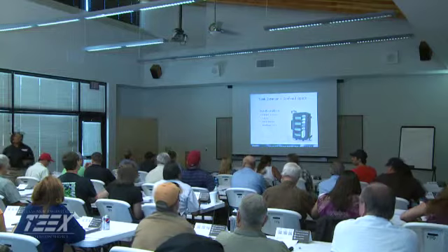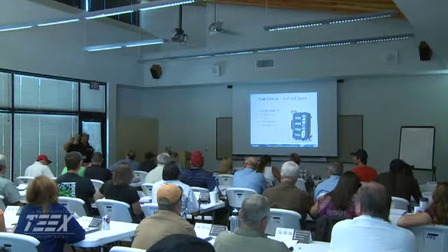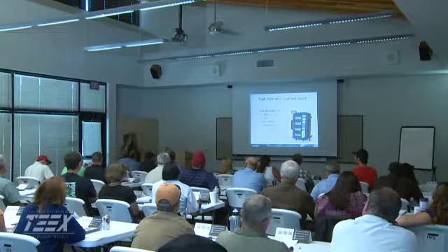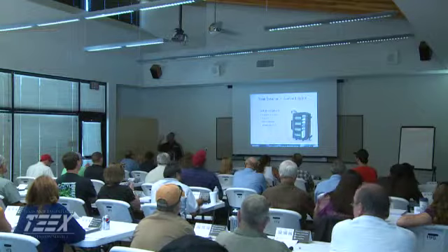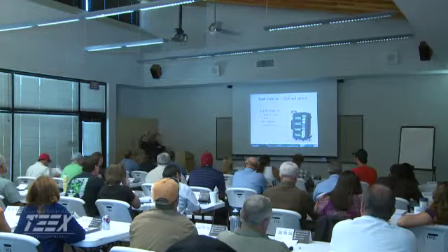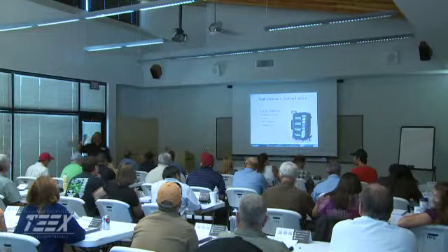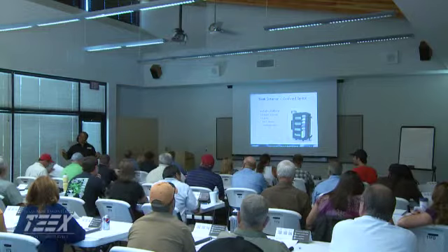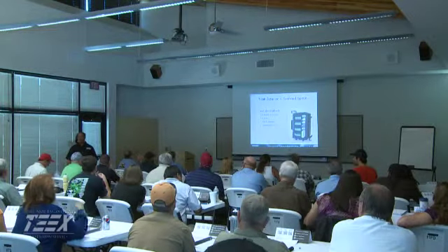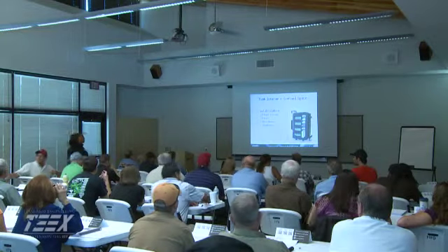It's real big. You're absolutely right. It is real big. Question: is there limited entry and exits? Yes. Is there a possibility of a dangerous gas or toxic atmosphere? Yes. Is it designed where we can stay in there for at least 8 hours or so, or continuous occupancy? No. So is it a confined space? Absolutely. Those are the criteria there.